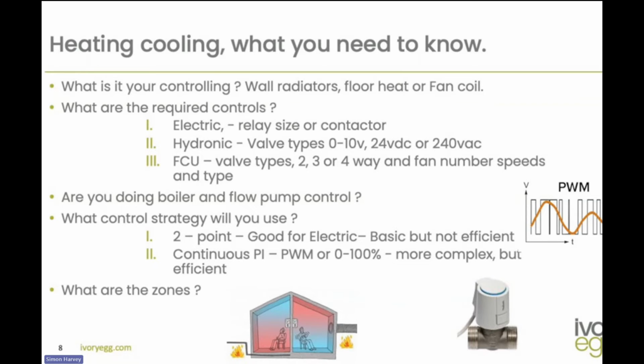You've got PWM, which is pulse width modulation, or a continuous output, which is something between 0 and 100%. If we look at the pulse width modulation strategy, basically it's a lot of pulses. It pulses the load on and off, on and off, on and off, until it starts to see the room temperature increasing closer to the set point. As this starts to increase to the set point, the pulse widths become a bit smaller, okay? So it fine tunes the output to pulse for less time and with fewer pulses to keep it closer to the target. So it's not busting over the target and then going under the target. It's just constantly keeping it within range, okay?